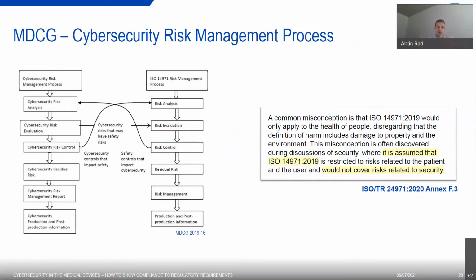However, you do have influences between the two. You have security issues and safety issues, and they might influence each other. For instance, a security measure such as a login window might lead to a safety risk, such as the device not being available when the password is lost, so you cannot treat the patient. If you have a strong password where the doctor needs 3 hours to write the password and get the 2-factor authentication password to get access to the device, a patient might already die. So in that case, you have influences between security measures and safety measures. And as always with medical devices, safety is the one that is more important for the patient. You don't want to kill the patient. That's the thing you should always consider.